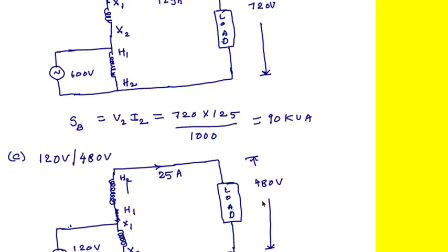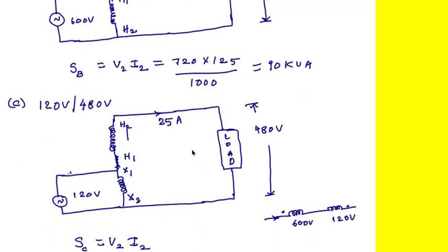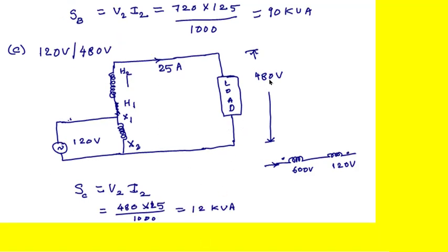The HV winding is connected in series with the load, and the current capacity of the HV winding is 25 amperes, which becomes the load current. The load voltage is 480 volts. So the kVA rating SC = V2 × I2 = 480 × 25 ÷ 1000 = 12 kVA.